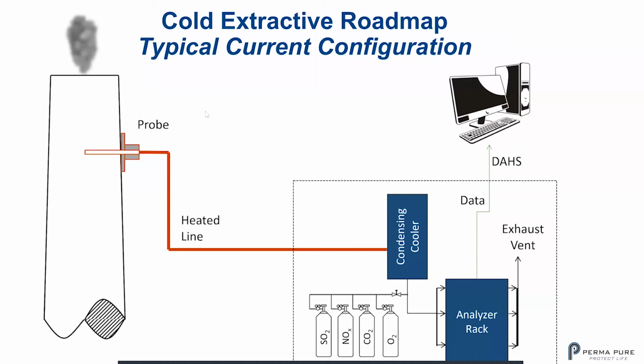So here is a typical cold extractive roadmap, a typical configuration. You have your probe in your stack, you have your heated line. Your heated line goes to a condensing cooler. Here you have your sample, your calibration gases, and here's your analyzer rack, and then your data goes to your computer.